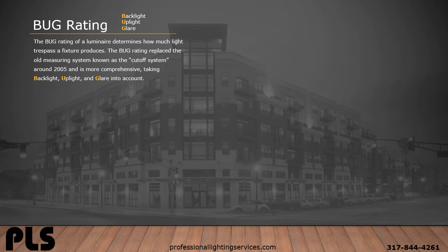Have you ever heard of a BUG rating? The BUG rating of a luminaire determines how much light trespass a fixture produces. The BUG rating replaced the old measuring system known as the cutoff system around 2005, and it's more comprehensive, taking backlight, uplight, and glare into account.